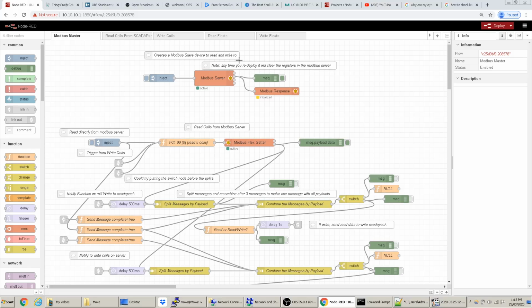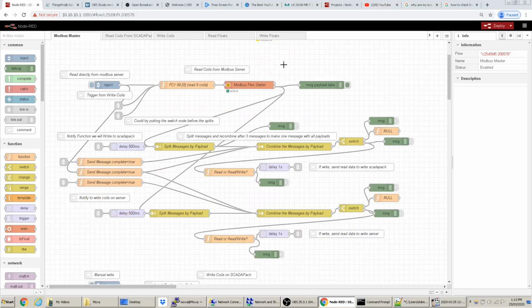As you know, we've got a Modbus server. We've got the ability to read from the Modbus server. So we'd hit this, boom, we'll read. This is going to trigger this guy, and this guy's going to clear both of these because we're just reading, so we don't need to write to Scadapack.